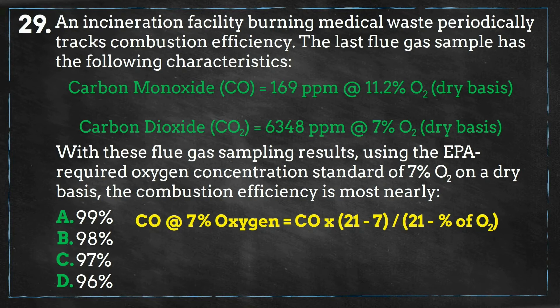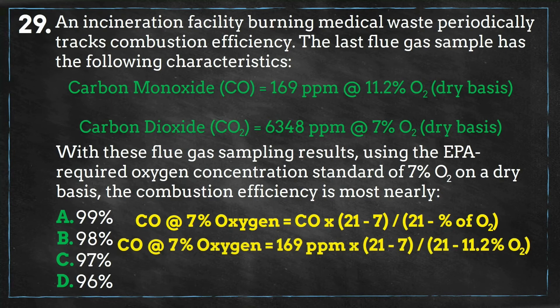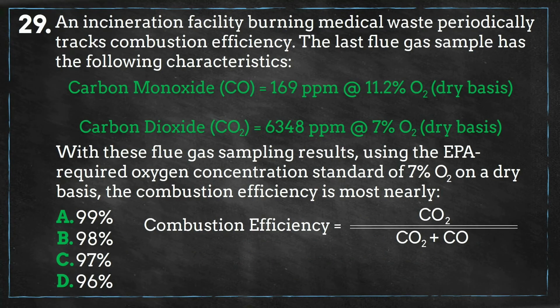This equation uses the atmospheric oxygen percentage of 21% to get an approximate value of what the concentration would be at 7% oxygen. The oxygen level at which the carbon monoxide measurement is taken is 11.2. So we will plug that into our equation, along with the carbon monoxide concentration, and we get a value of 241.4 ppm for the equivalent carbon monoxide concentration.